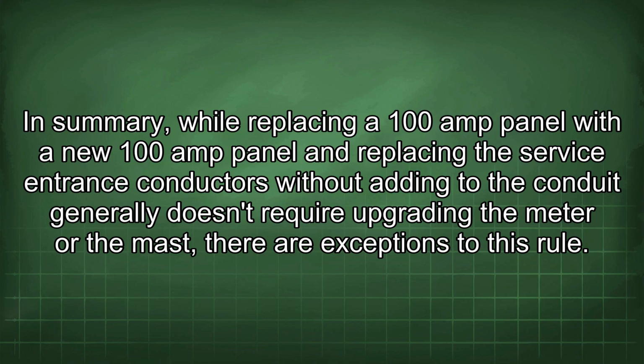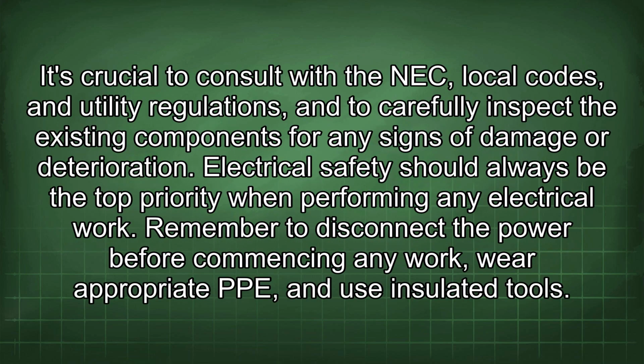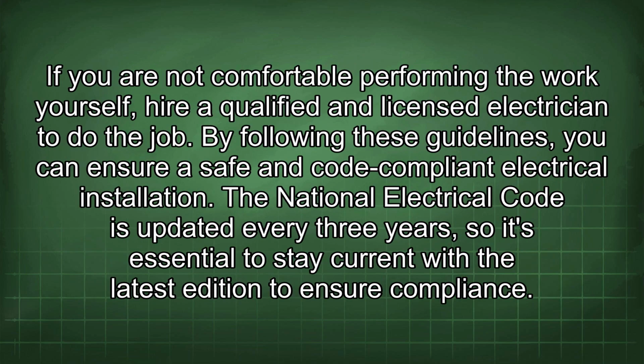In summary, while replacing a 100 amp panel with a new 100 amp panel and replacing the service entrance conductors without adding to the conduit generally doesn't require upgrading the meter or the mast, there are exceptions to this rule. It's crucial to consult with the NEC, local codes, and utility regulations, and to carefully inspect the existing components for any signs of damage or deterioration. Electrical safety should always be the top priority when performing any electrical work. Remember to disconnect the power before commencing any work, wear appropriate PPE, and use insulated tools. If you are not comfortable performing the work yourself, hire a qualified and licensed electrician to do the job. By following these guidelines, you can ensure safe and code-compliant electrical installation.